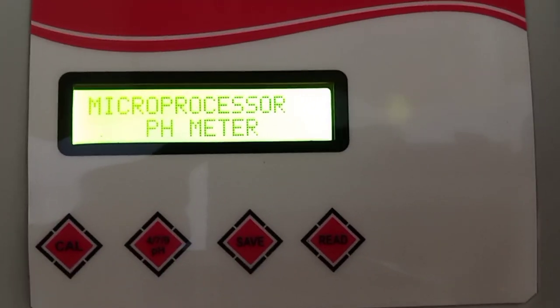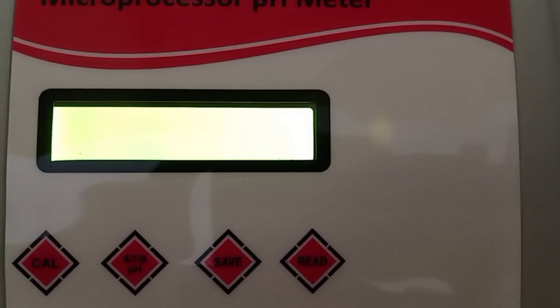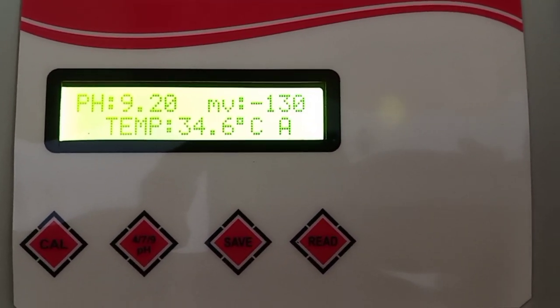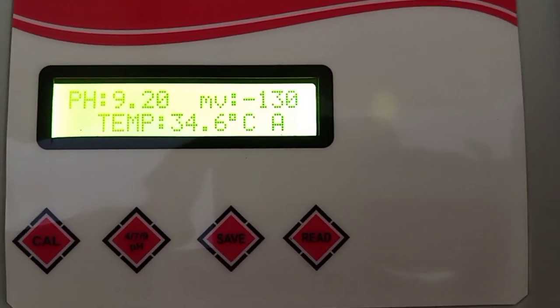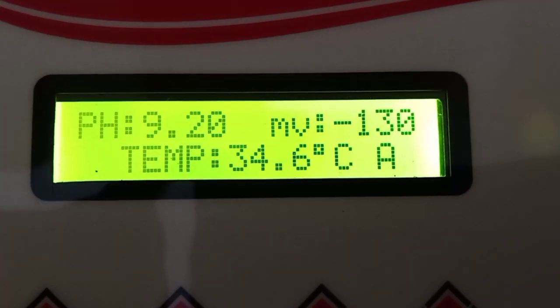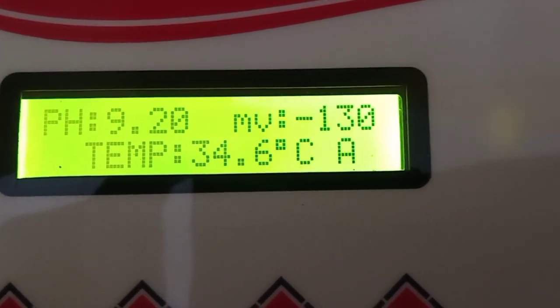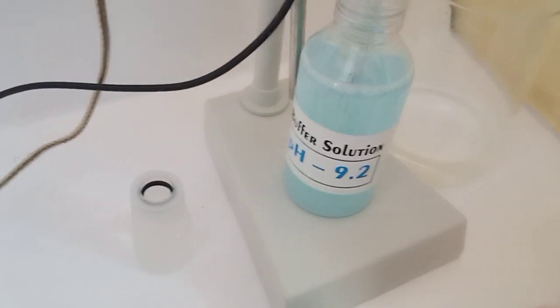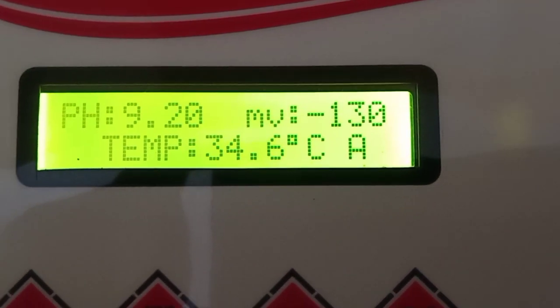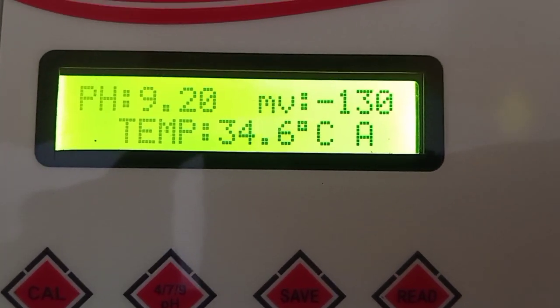Now calibration is successful. After the calibration is successful, the machine automatically comes into the measurement mode. Now the machine is showing pH value, that is 9.20, buffer is 9.20, millivolt, and temperature value. A stands for automatic temperature compensation.